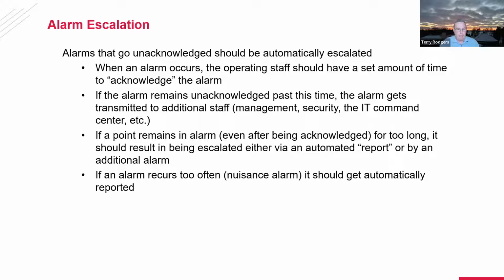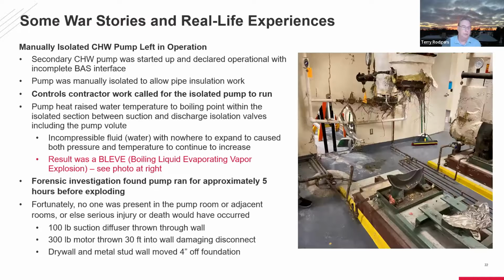And then, of course, you have your nuisance alarms. So if something goes into alarm, gets acknowledged, an hour later it goes into alarm, gets acknowledged, and they just keep doing this and resetting it, that in and of itself should generate an alarm that says we have a problem that's recurring and needs to be addressed through a root cause or some other way of doing this.